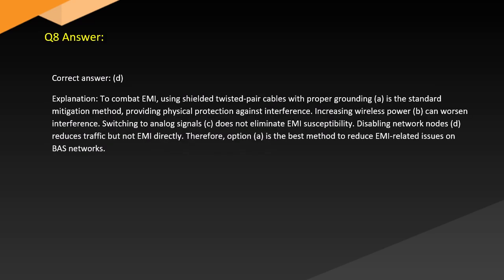Answer. Correct answer: A. Explanation. To combat EMI, use shielded, twisted pair cables with proper grounding. A is the standard mitigation method, providing physical protection against interference. B, increasing wireless power, can worsen interference. C, switching to analog signals, does not eliminate EMI susceptibility. D, disabling network nodes, reduces traffic but not EMI directly. Therefore, option A is the best method to reduce EMI issues on BAS networks.